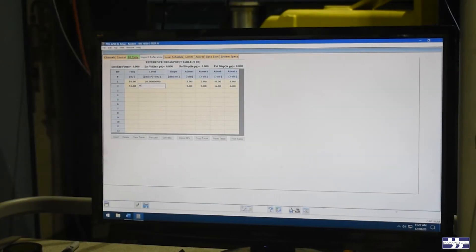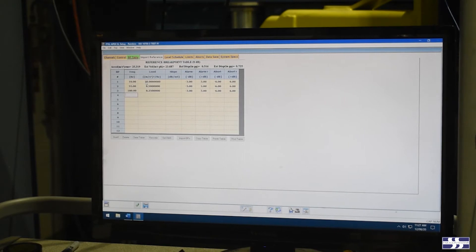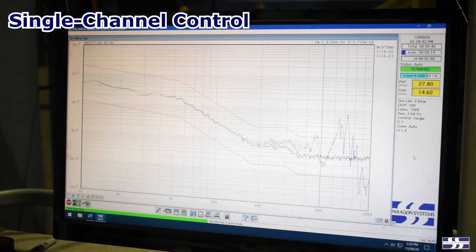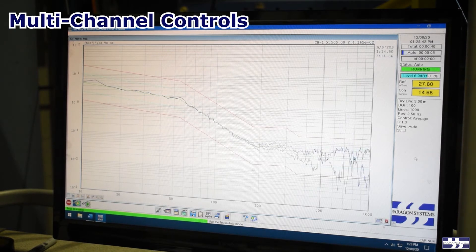The vibration controller can use these additional out-of-tolerance accelerometer channels and, by averaging them along with the in-tolerance table surface acceleration channel, optimize all of the channels by utilizing the full positive and negative width of the test profile tolerance.